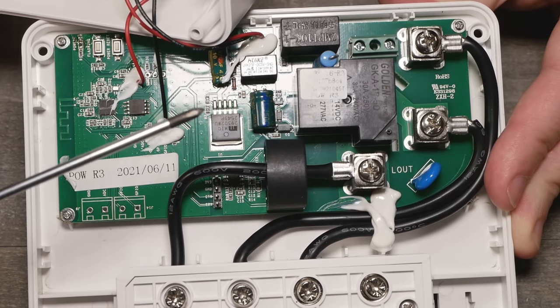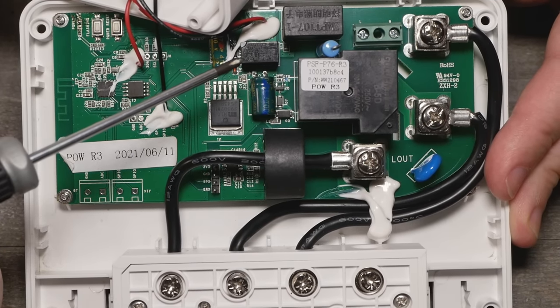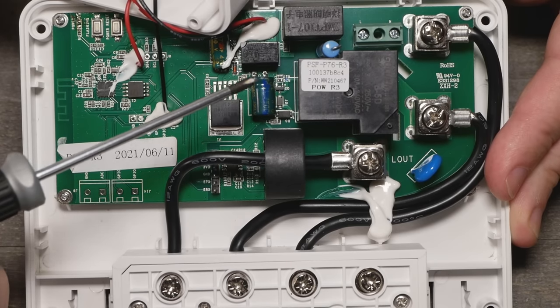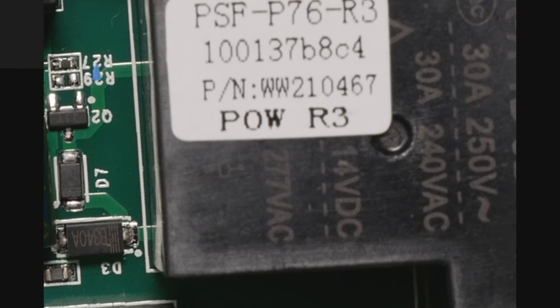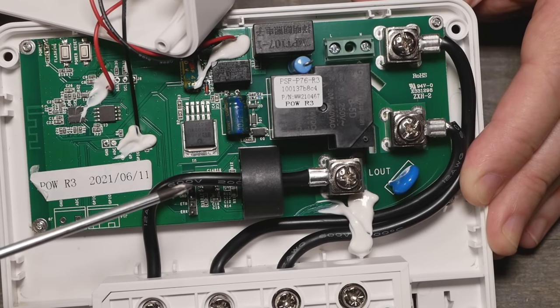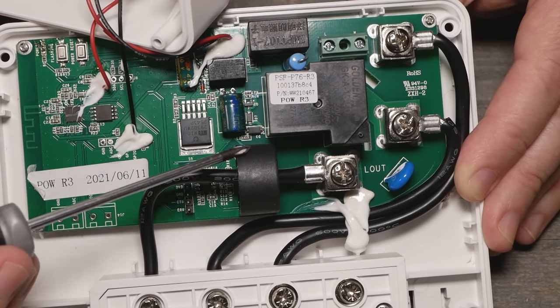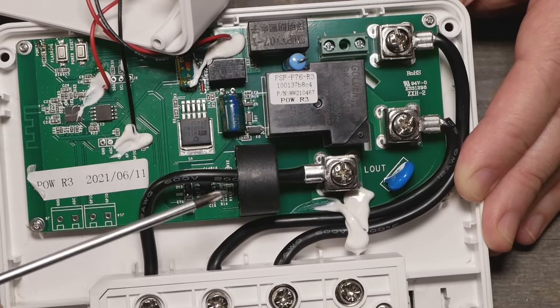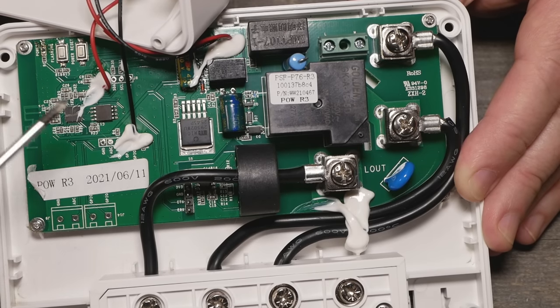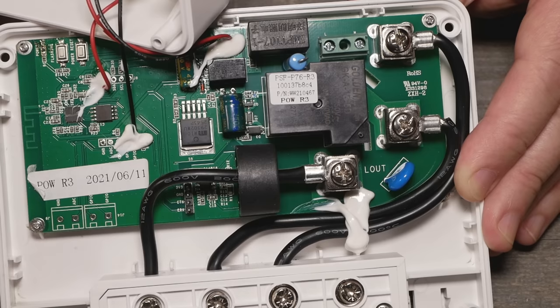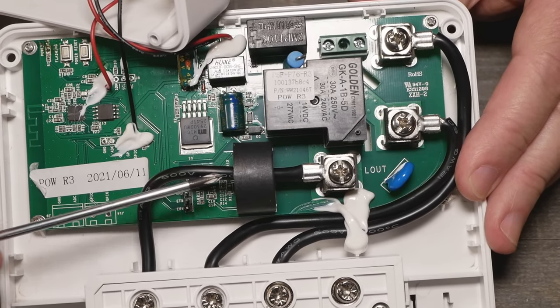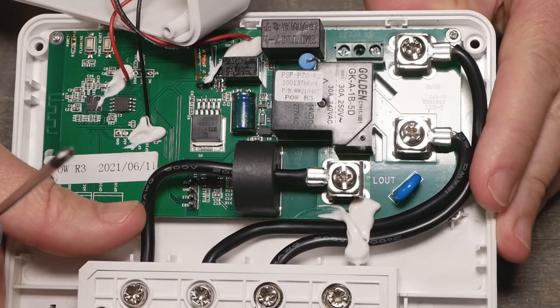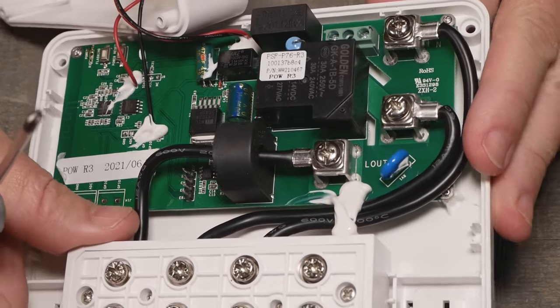Now, what's different about this is, from what I remember, when we looked up, basically there was a relay switch that then kicked the other relay on. And this is a full 30-amp, 250-volt-rated relay. And you'll notice something weird here. This little round thing, a lot of people will call that, some call it the donuts, or the current transformer, or people know them as SCTs, but those are split-core transformers. These are not split. The wire just passes through. If you've seen some of the power monitoring stuff, that's how this is done, just measures one of the leads going through.